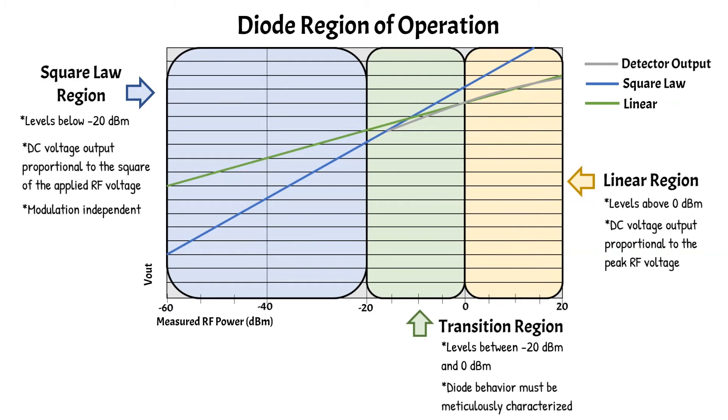The linear region is found at levels above zero dBm, where the DC voltage output is proportional to the peak RF voltage. The transition region of a diode sensor is at levels between negative 20 dBm and zero dBm. Diode behavior must be meticulously characterized within this region to produce accurate power measurements.